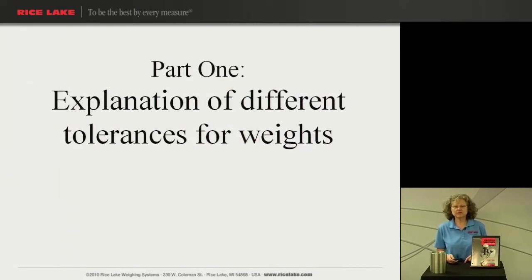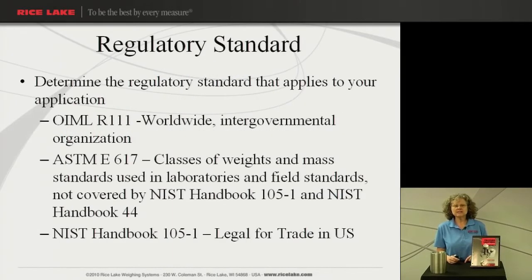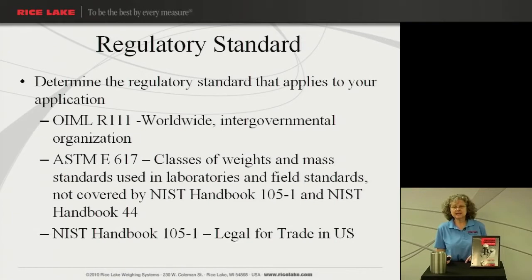Part 1: explanation of different tolerances for weights. First thing to consider is whether you have any regulatory requirements, or which regulatory requirement would be most applicable for you. So depending on where you're located and what your application is, one of these regulatory requirements will be the best. OIML R111 is a worldwide intergovernmental organization. If you're anywhere besides the United States, this might be the best choice for you. If you're doing business worldwide, you might want to look at these guidelines also to make sure that your product can be used anywhere that you might be selling to.